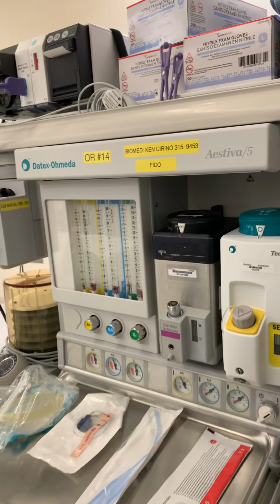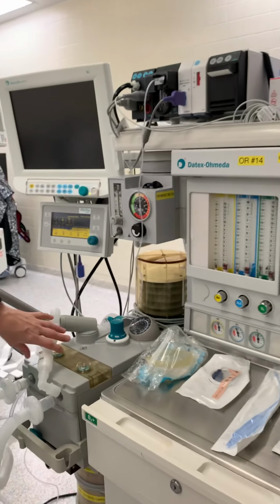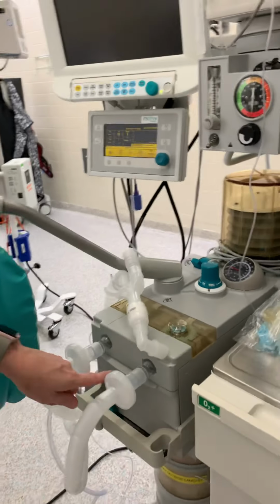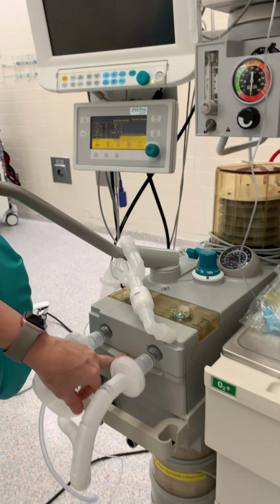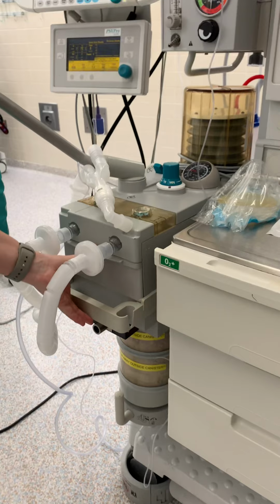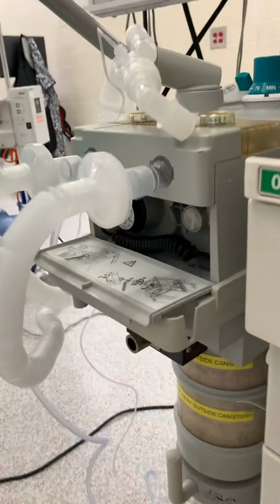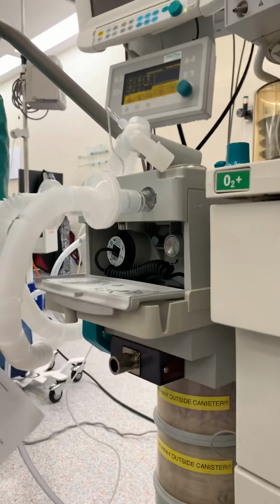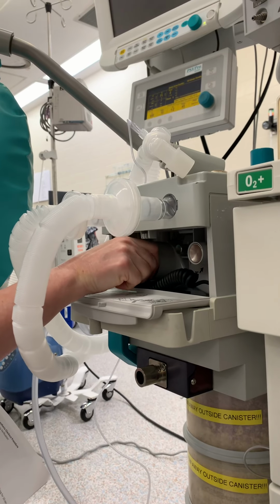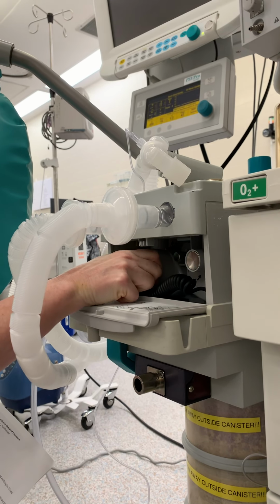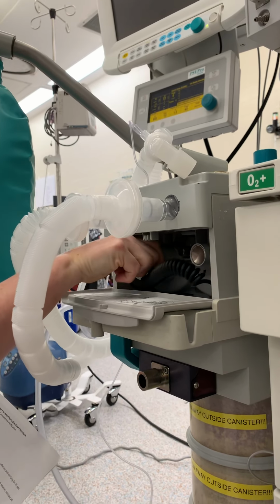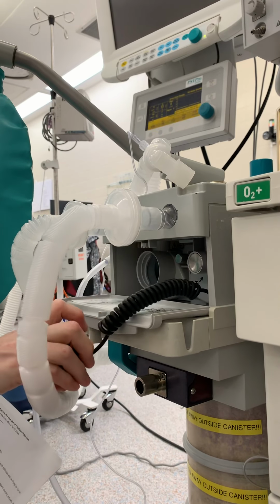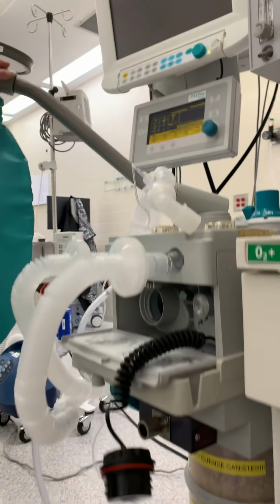Number 6, calibrate O2 sensor. In every machine, again, it's a different place, and on the Aestiva it's going to be located right here. You just pull down, and you'll see your O2 sensor right here, and you just want to loosen to the left. Remember, lefty loosey, very gently undo it, and then you can just let it hang. And then the rest of this is done on the ventilator settings.